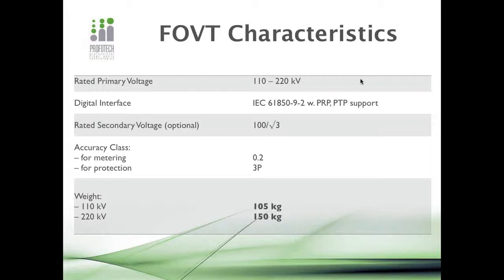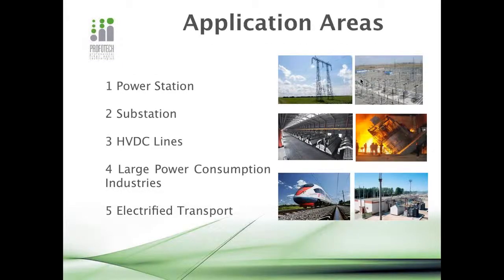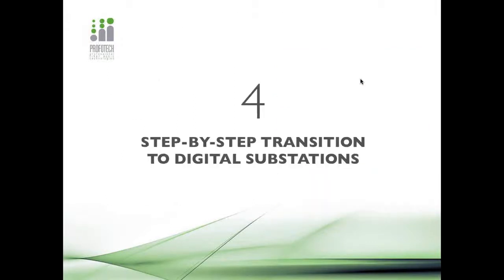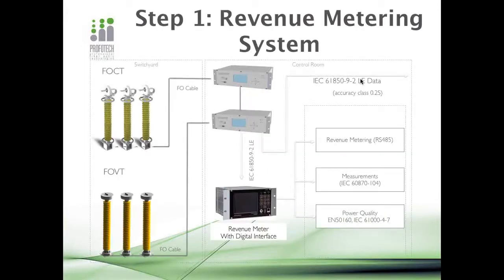And its weight is a little bigger than the optical current transformer, but if you remember the weight of the conventional voltage transformer, the oil insulated voltage transformer, then it's much, much lighter again. The application areas of these devices are shown on the slide. That's basically the most power-consuming industries and the power energy facilities themselves: power stations, substations, HVDC lines, the industries, and electrified transport.